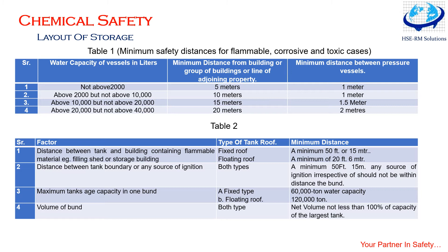Low division walls between tanks within the bund are recommended. Sometimes it may not be practicable to provide full bund capacity; in such cases, provisions may be made for separate impounding areas into which liquid spillage may be directed. The bund should be far enough from the side of the tank to prevent a jet of liquid from jumping over the corners of the bund, and corners should be rounded. The bund should be provided with drains. The maximum bund height recommended in some literature is two meters. There should be a minimum of two access points on opposite sides of the bund to allow safe access and escape in all wind directions.